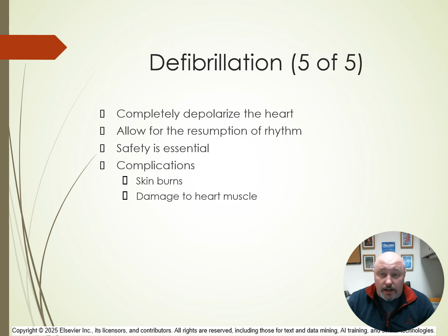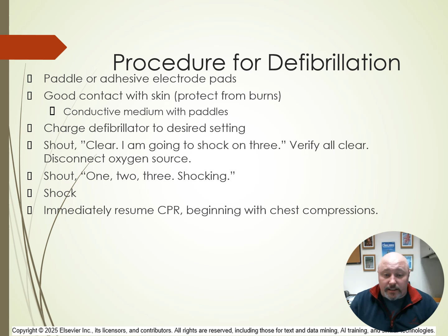You would begin with the paddle or adhesive pad electrodes, and make sure you've maintained good contact with the skin to help protect the patient from burns. You want to charge the defibrillator to the desired setting. Shout clear, I'm going to shock on 3, and then verify that everyone has heard you and is actually clear of that patient. Also keep in mind disconnecting any oxygen source to remove any risk of fire. Shout 1, 2, 3, shocking, and shock. From there, immediately resume CPR, beginning with chest compressions.